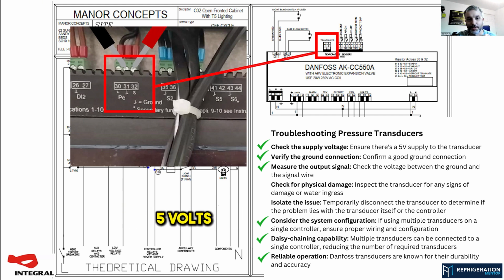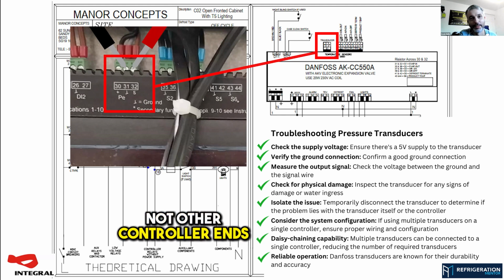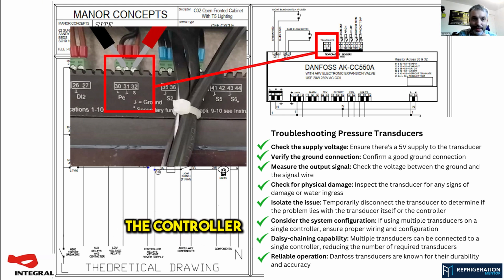But yeah, check you've got your 5 volts coming out, check you've got a signal coming back. Things can drag it down. Water in the plug will drag the 5 volts down. It's only got a very limited amount of current it can put out. It'll protect itself. The chances are you take the fault away, it'll recover. You can also take the wires out of the plug or take the plug off the transducer. If your 5 volts comes back, the fault is at the transducer end, not at the controller end. It's quite rare to kill the output from the controller. It's much more common that something drags it down in the field.